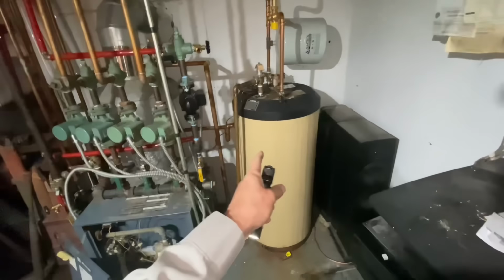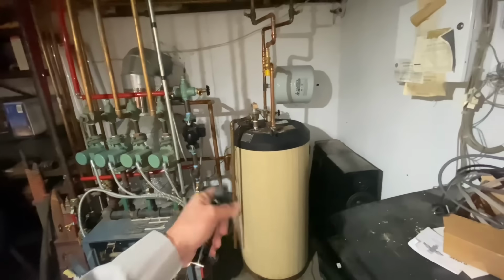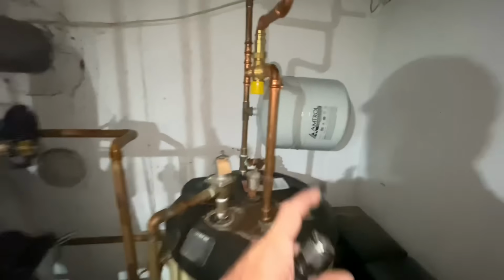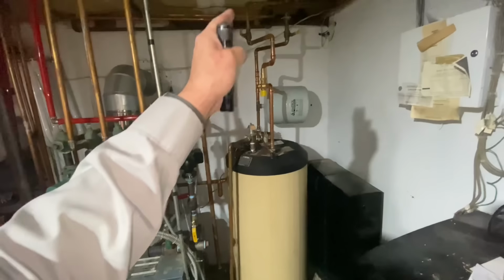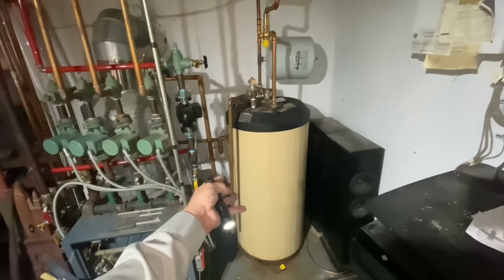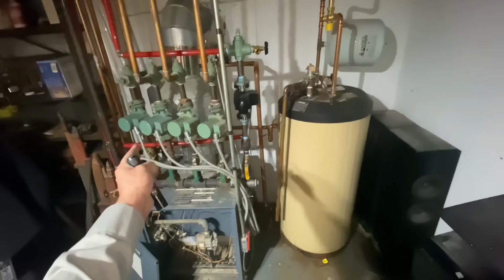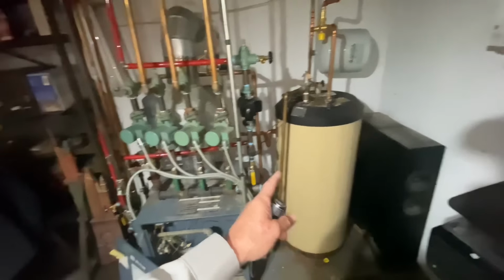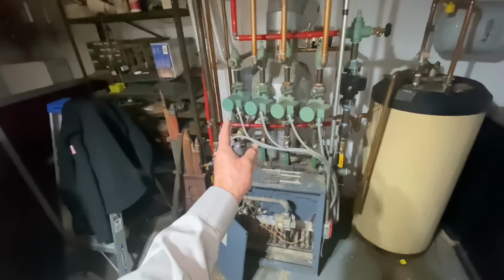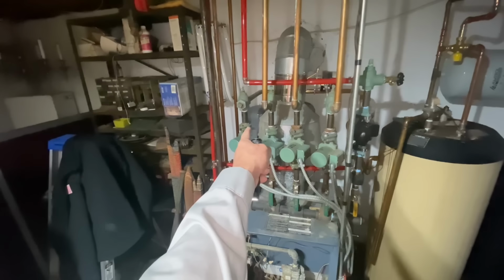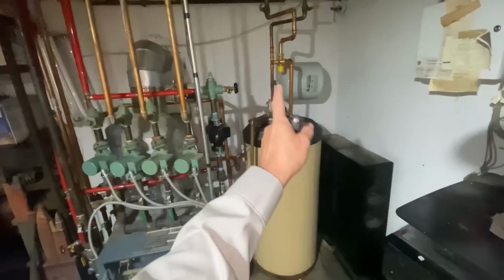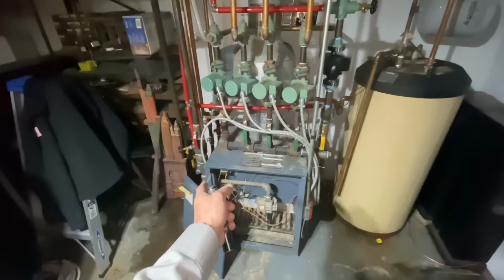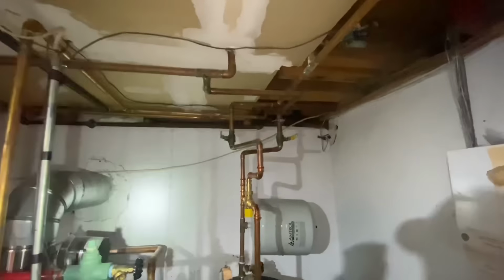But this water heater failed. We had tank within tank failure. And what that means is, and by the way, this is installed in the wrong orientation. Okay? What that means is that we have domestic water inside one tank and another tank with hydronic water. And the hydronic water heats that domestic water tank. The tank failed, causing the pressure relief valve on the boiler to lift. After the expansion tank is full, it can't absorb any more pressure because the tank is leaking into the hydronic side and causing problems with the boiler.